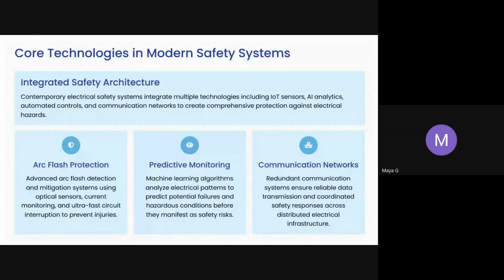One of the main hazards in electrical systems is arc flash. Advanced arc flash protection and mitigation systems use optical sensors, current monitoring, and ultra-fast circuit interruption to prevent injuries, acting within 1 millisecond.